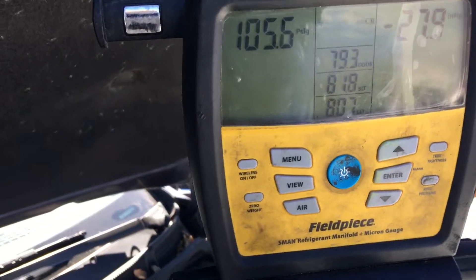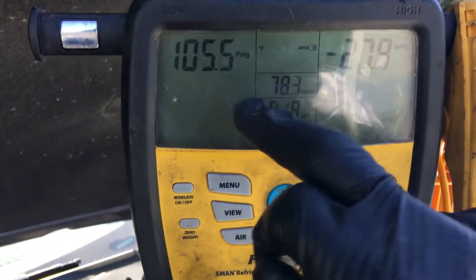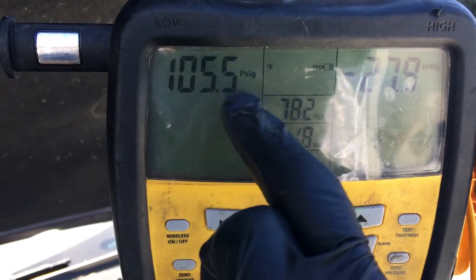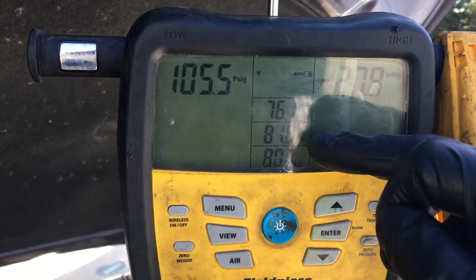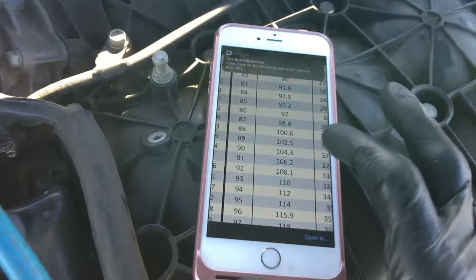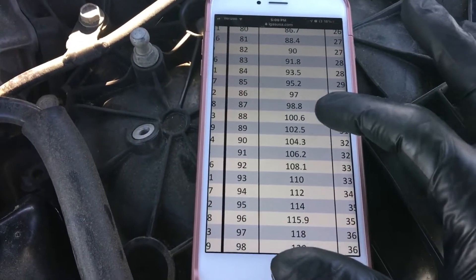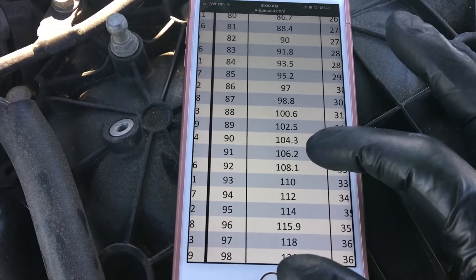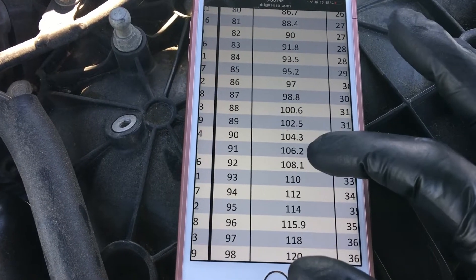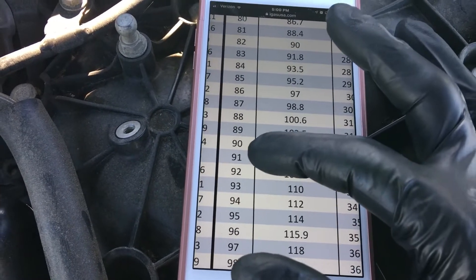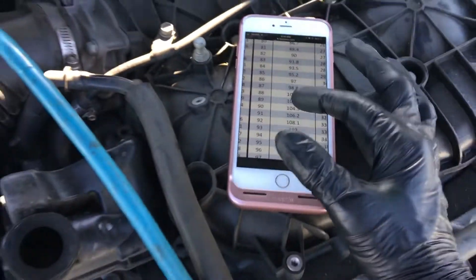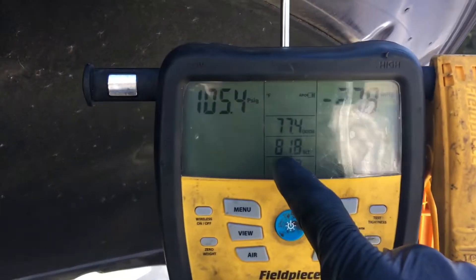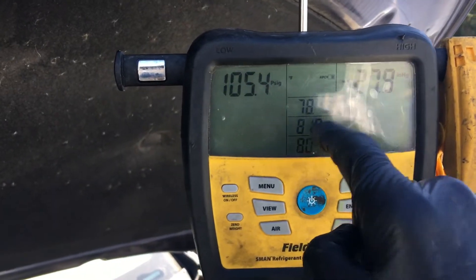My pressure is 105 psi, 105.5 psi. I'm using my suction line temperature clamp and that says 81 degrees. This is R134. So at 105 psi — there's 104, 106 — we're somewhere right in the middle. So my temperature should be about 90 and a half degrees. But I'm at 81. That's almost 9 degrees difference.